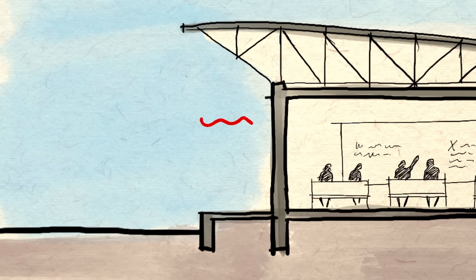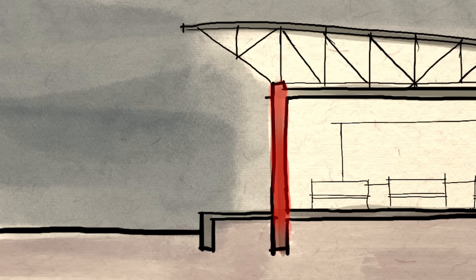With the nights being cooler, the heat of the day can be stored in the walls while class is in session, protecting the classroom from the bulk of the heat. During the night, when the classroom is empty and the temperatures drop outside, that heat is slowly released from the walls and quickly disposed of through ventilation.